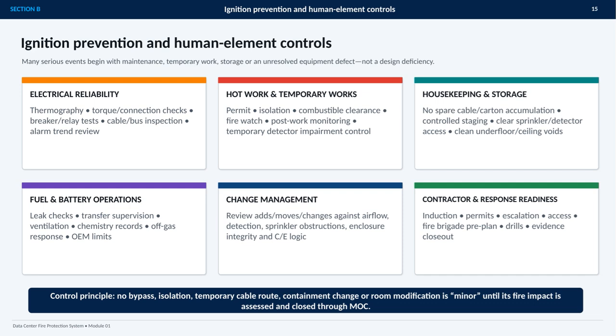Fuel and battery operations also require leak checks, supervised transfers, ventilation, chemistry records, off-gas response, and adherence to manufacturer limits. Finally, every addition, relocation, or modification should be reviewed for impacts on airflow, detection, sprinkler coverage, enclosure integrity, and control logic. Contractors need induction, permits, escalation routes, access control, response preplans, drills, and documented closeout.